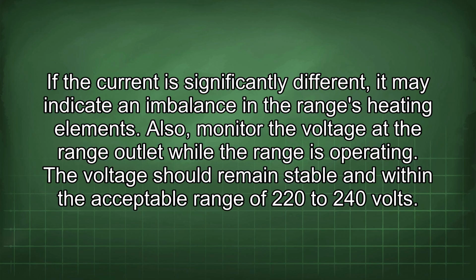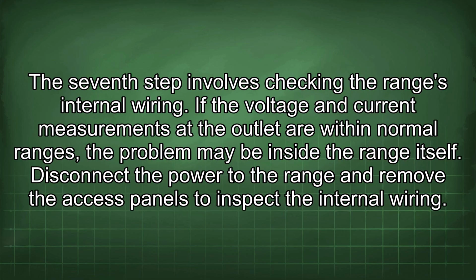Also, monitor the voltage at the range outlet while the range is operating. The voltage should remain stable and within the acceptable range of 220 to 240 volts. The seventh step involves checking the range's internal wiring. If the voltage and current measurements at the outlet are within normal ranges, the problem may be inside the range itself.